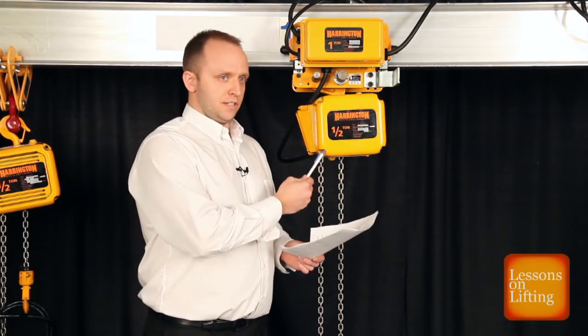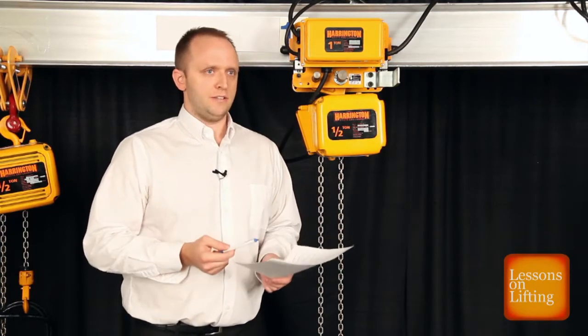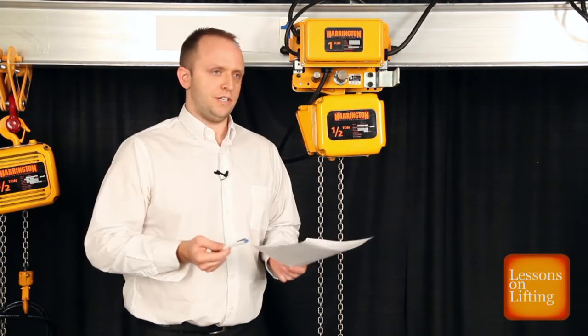Another way to tell is to actually physically look inside the unit, underneath either one of the covers. If you see a VFD inside there, that will tell you that you have a dual-speed unit and a voltage change is not possible.